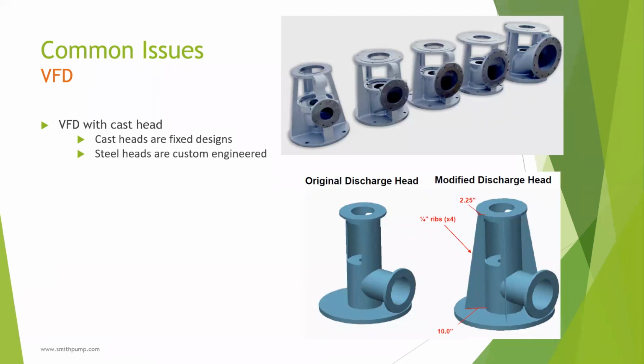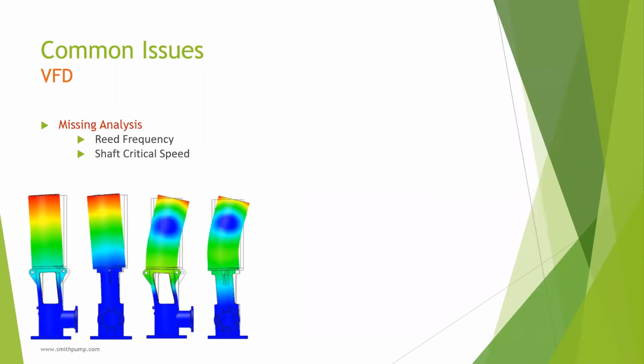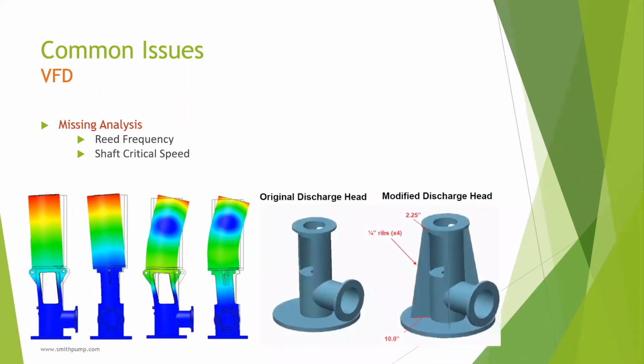It all starts with an analysis performed by the manufacturer. We always recommend performing analysis of the pump if running on a VFD. This will let the design team fix potential issues before fabrication. So the reed frequency basically determines the discharge head and motor natural frequency. The parts are modeled in 3D and calculations are run based on expected operating range. The head may need design modifications to increase or decrease its natural frequency.